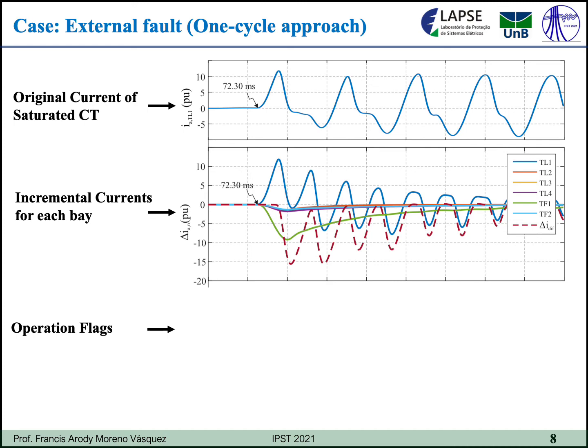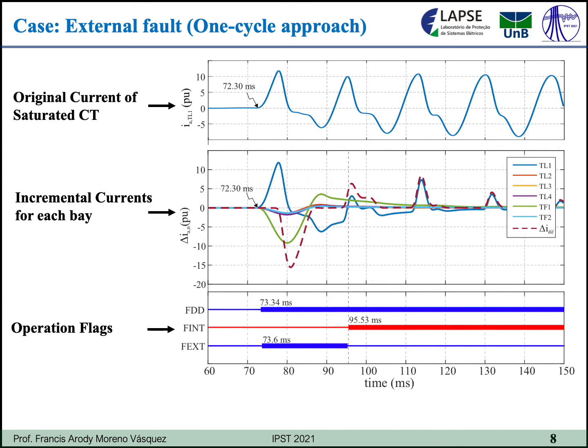Now I repeat the result of the simulation of an external fault with CT saturation, and here the proposed technique will be tested, but using a one-cycle window for the calculation of incremental currents. The result is as shown. It is hoped that the algorithm does not operate in this condition. However, it can be noticed that the function erroneously identified an internal fault at approximately 95 milliseconds. It occurs because of the window size of one cycle, which causes the incremental differential current to change its polarity due to the saturation of the CT.